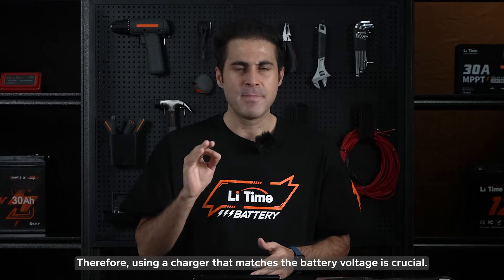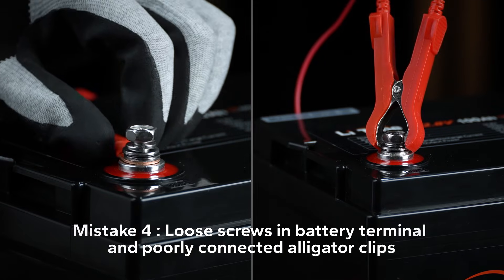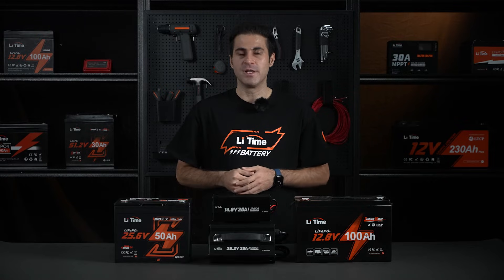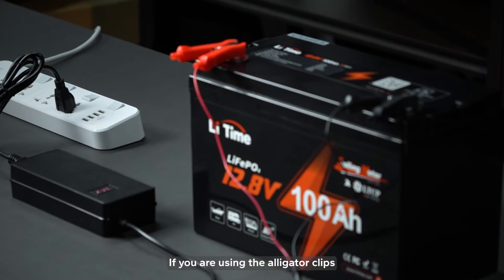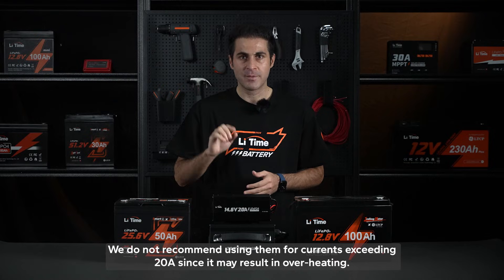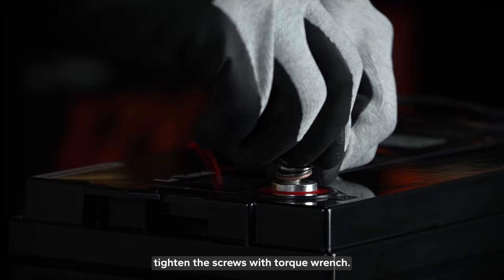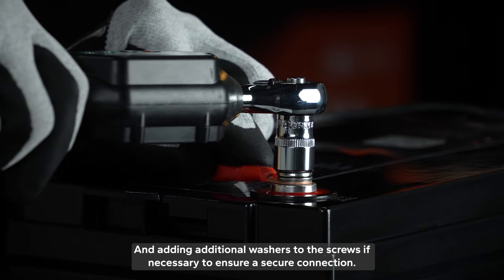Therefore, using a charger that matches the battery voltage is crucial. Last but not least, loose screws in battery terminals and poorly connected alligator clips. This may lead to overheating, melting the battery terminals, or result in circuits not working properly, leaving batteries unable to charge or discharge normally. If you are using alligator clips, make sure to check the ampere rating of the charging current — we do not recommend them for currents exceeding 20A, as it may result in overheating. If you are connecting wire lugs to terminals, tighten the screws with a torque wrench and add additional washers to the screws if necessary to ensure a secure connection.